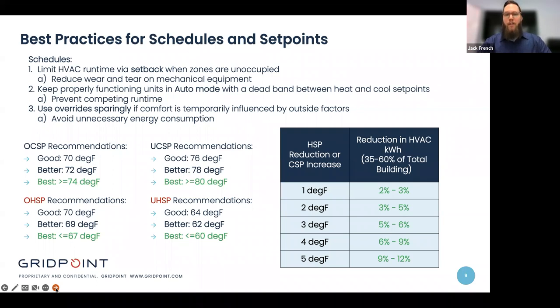And then finally, use overrides or changing set points sparingly, when comfort is temporarily influenced by outside factors. You may find yourself in a position where folks on site have to prop open a door to receive a shipment, or there's increased foot traffic during lunchtime. That may prompt a comfort concern, and using an override sparingly, which may run for 30 minutes, 60 minutes, 90 minutes, and then allow the unit to return back to its scheduled set point, is going to avoid unnecessary energy consumption. And by doing so, also avoid excess wear and tear on mechanical equipment. So all of these schedule strategies are essentially trying to limit your HVAC runtime.